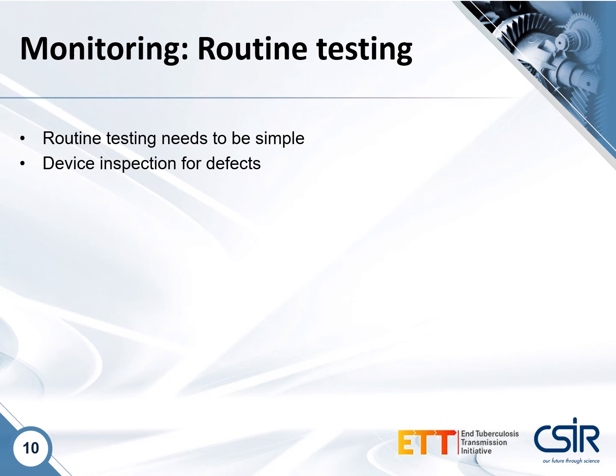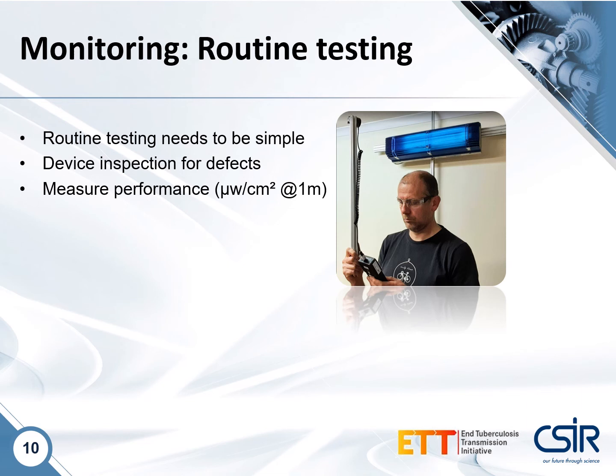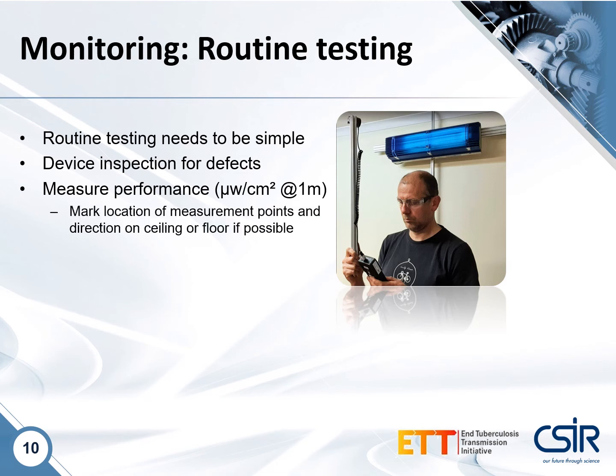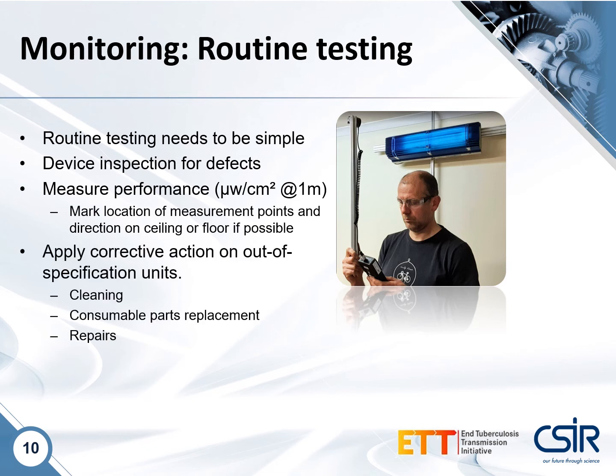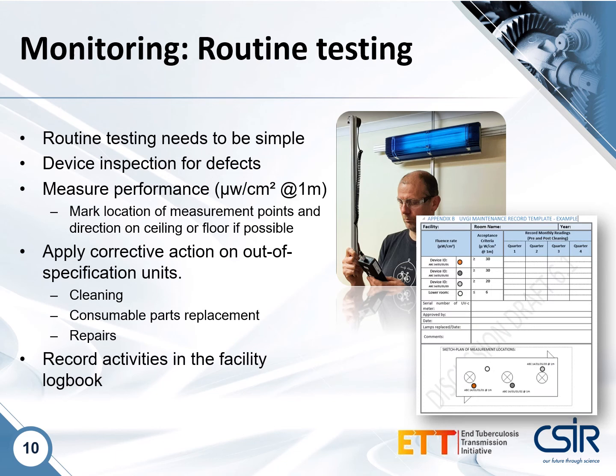And then with only the single device that you're going to measure on, you measure its irradiance at 1 meter. That's done using your radiometer. You can mark the location of measurement points on the floor or the ceiling so that these points are easily referenced and repeatable for future measurements. And you should apply then corrective actions for any out of specification units. And your corrective actions would include things like cleaning, replacement of any consumables, and repairs to the device. Then all of your activities need to be recorded in a facility logbook. An example is provided on the slide.